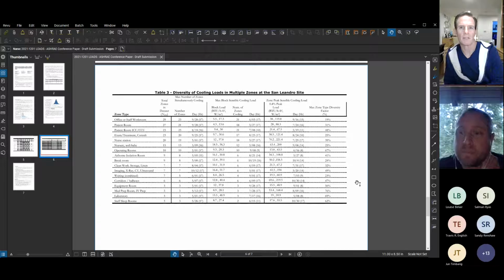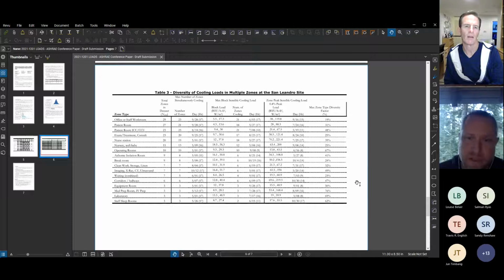But does it say whether or not there's any reheat happening? So the temperature measurement is after the reheat coil, so regardless whether the box is doing any reheat at the box, we're measuring the actual temperature being delivered to the room. Does that make sense? Yeah, totally.